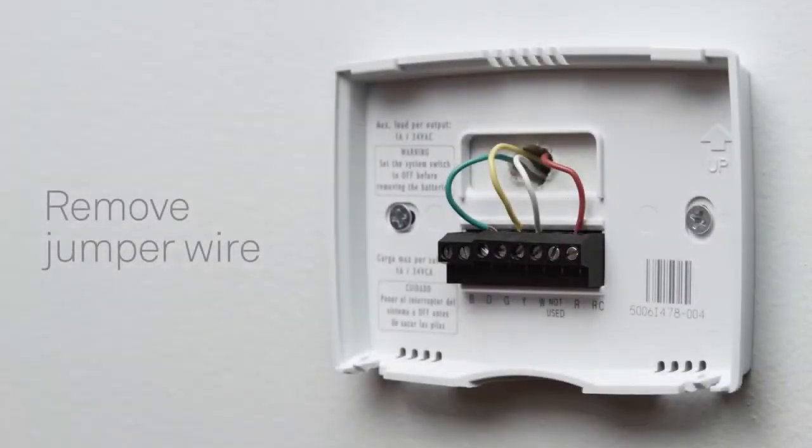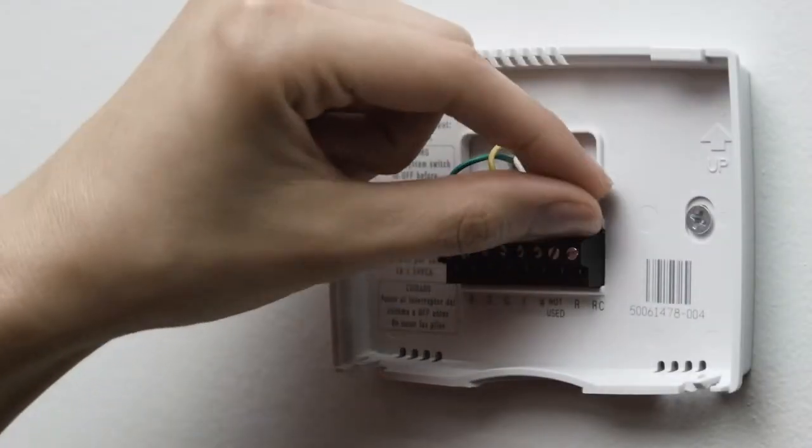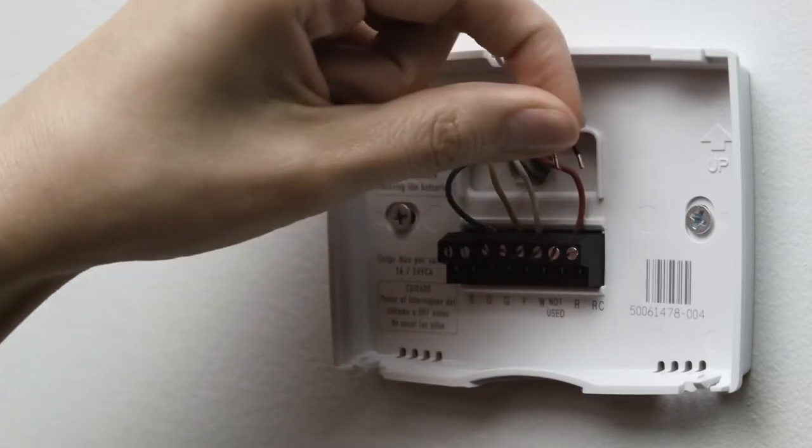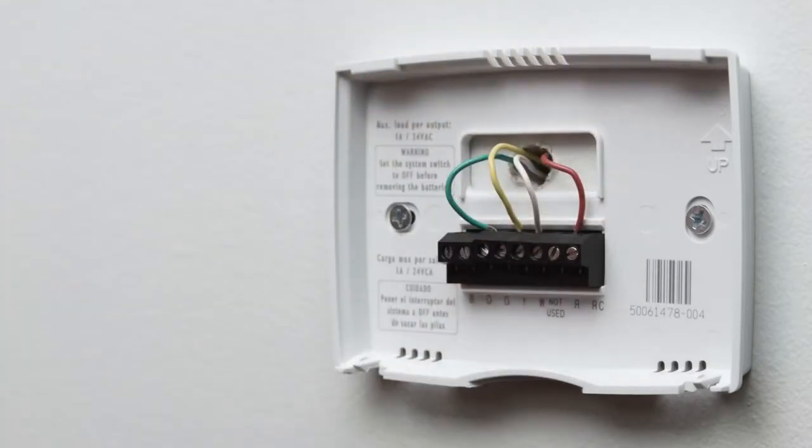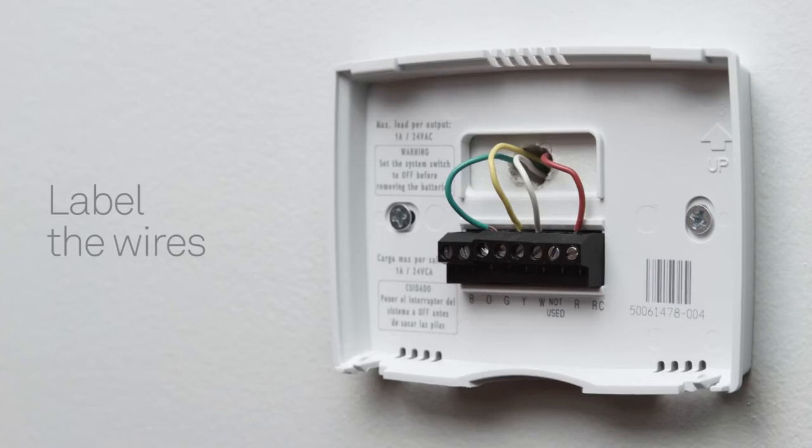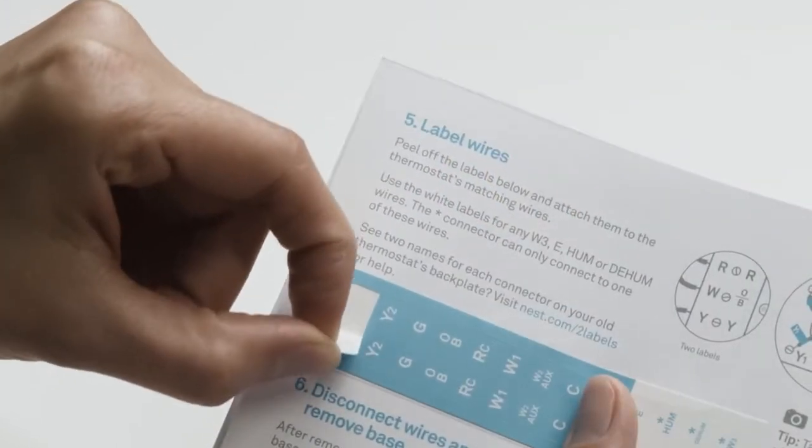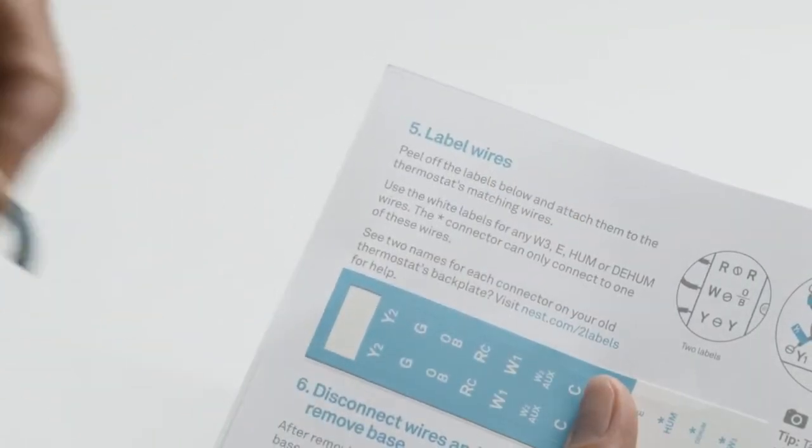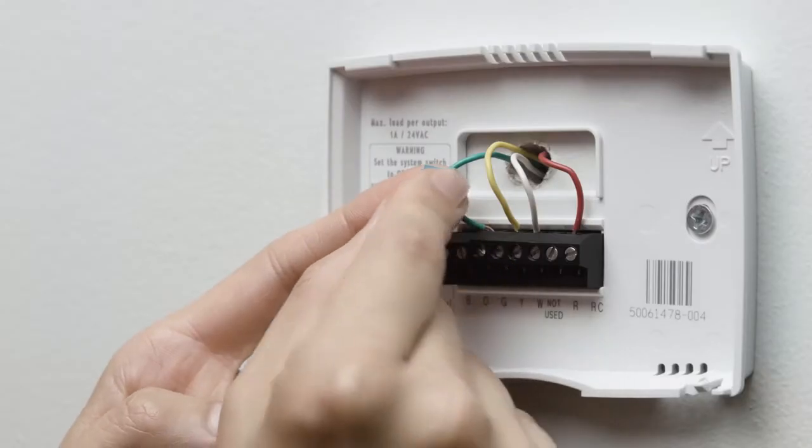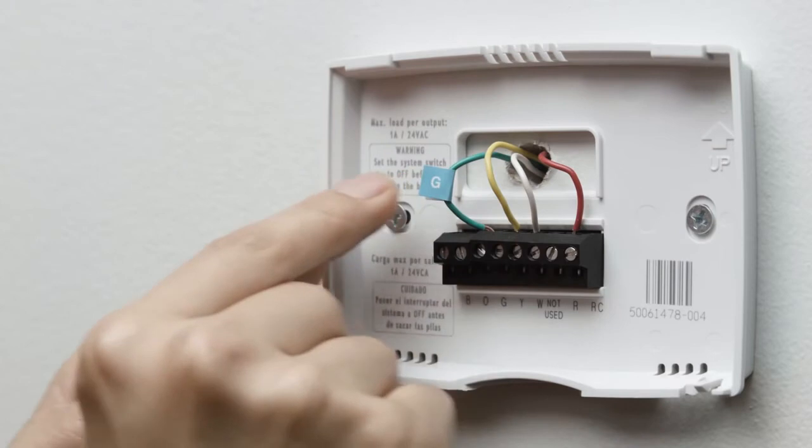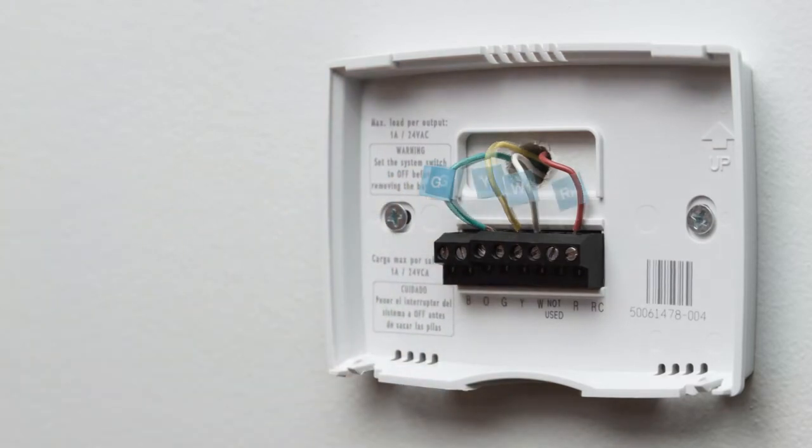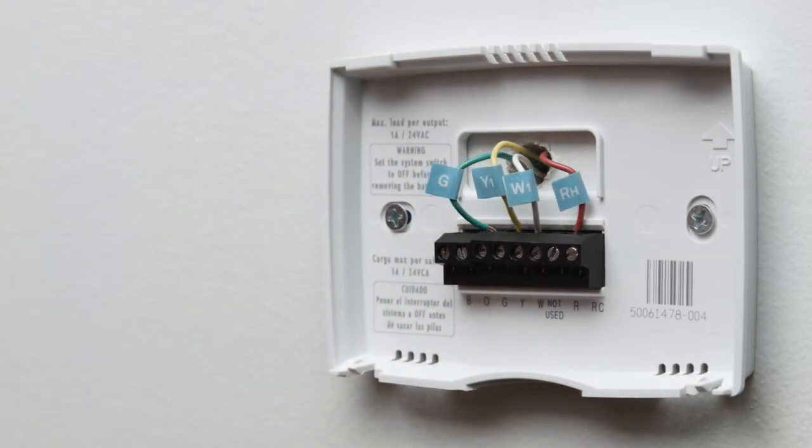If there's a jumper wire connecting one wire to another, remove it. You won't need it. Because every heating and cooling system is different, it's important to label the wires. Attach the labels in the installation guide to the matching wires. Then you can disconnect them from your old thermostat.